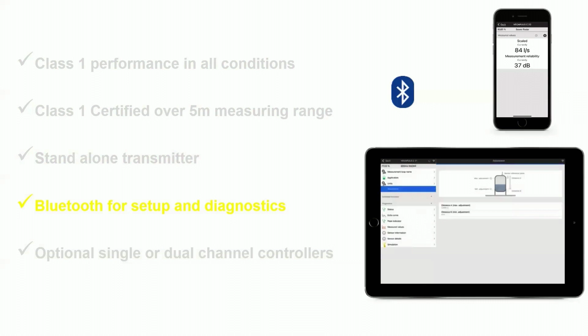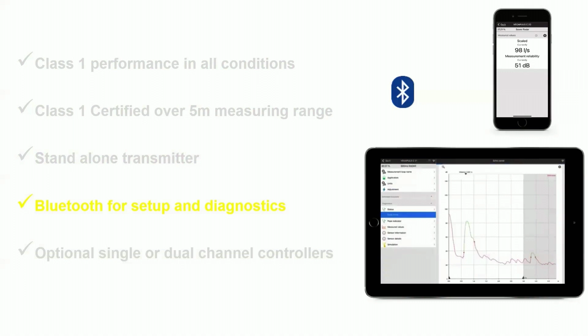The fourth point I wanted to touch on is Bluetooth. Bluetooth communication comes with all our radars and controllers as standard, and this provides a quick, simple, safe and secure way of connecting to the instruments. When we've looked at draft EDM standards previously, there's been talk of an Environment Agency officer or MCERTs inspector being able to look at a sensor's display and see its current status relative to the switch point or spill point. That doesn't have to be a physical display - it could be an app-based display, like what we've got showing on the screen. Bluetooth gives a lot of flexibility in setting the sensor up from a safe location, and it's extremely convenient for making sure you've set the instrument up right the first time round.